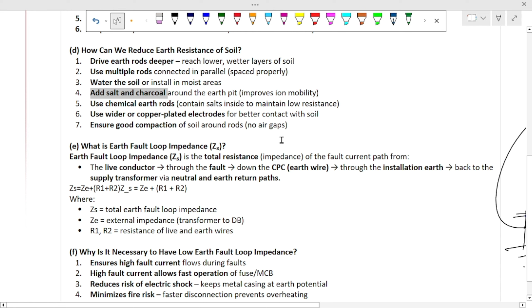Add salt and charcoal, this is very, very common. When you dig the hole to put in your earth rod, you add salt and charcoal to improve ion mobility and reduce resistance. In other words, use chemical earth rods, wider or copper plated electrodes, and ensure good compaction of soil around the rods with no air gaps.